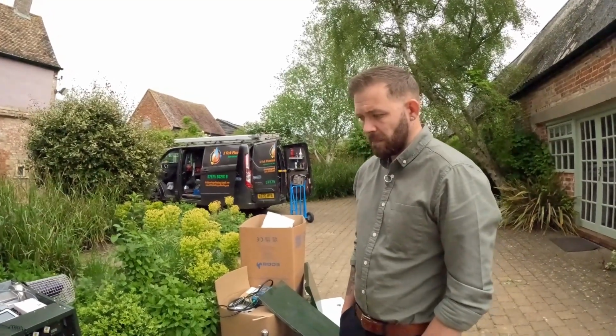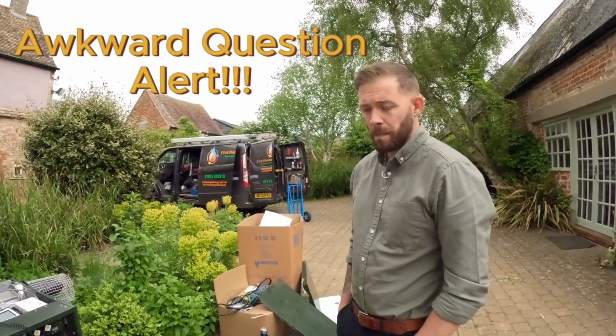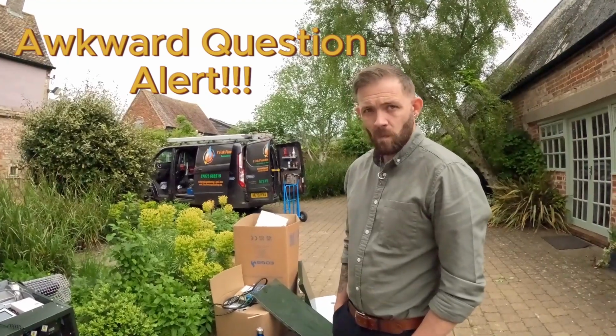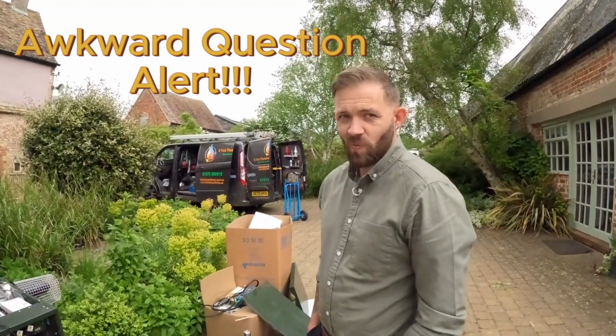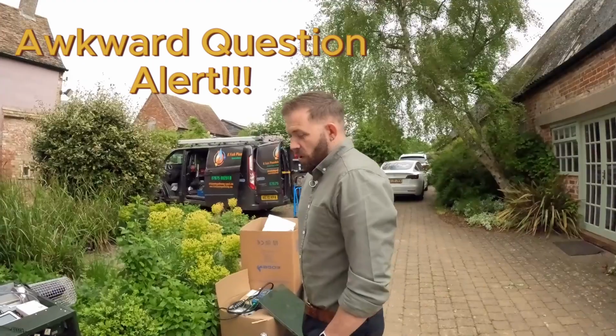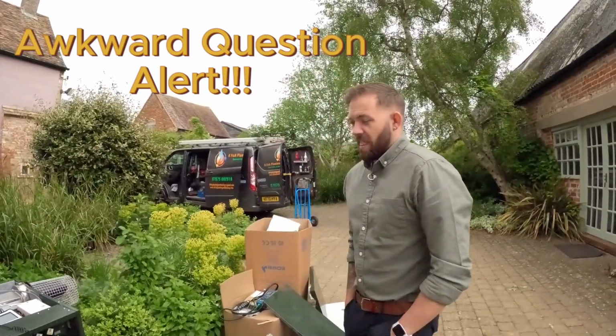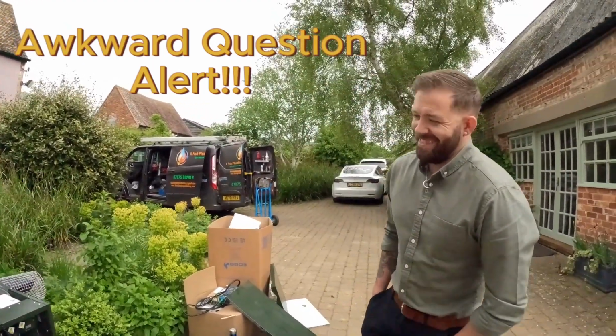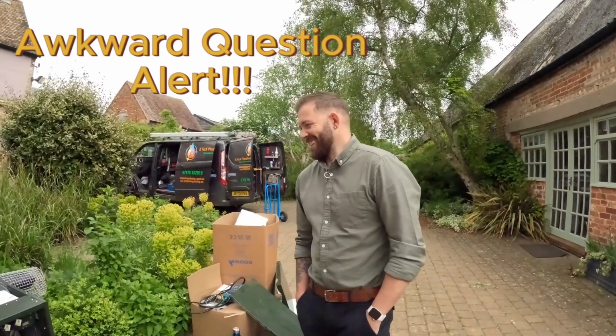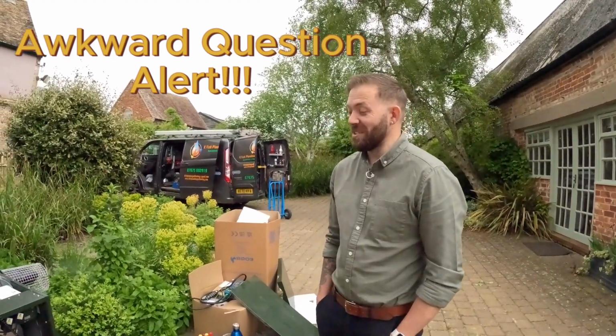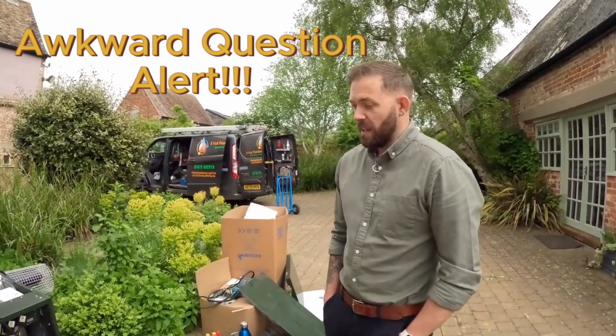From an installer's perspective, one last question: is there any issue regarding OFTEC? Because obviously there is an issue with other boiler manufacturers having a 2-stage burner, where if you're on your basic OFTEC, you shouldn't actually touch that 2-stage burner, technically. So have we got a problem with your burner on that point at all?